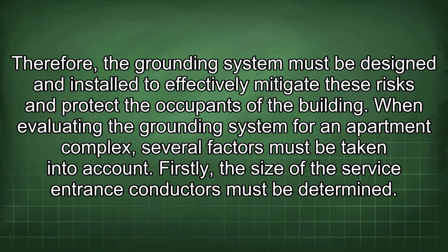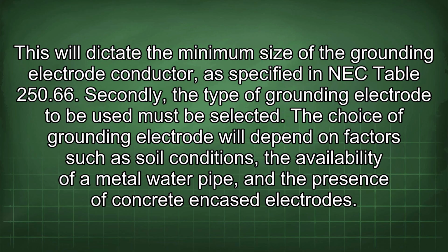When evaluating the grounding system for an apartment complex, several factors must be taken into account. Firstly, the size of the service entrance conductors must be determined. This will dictate the minimum size of the grounding electrode conductor, as specified in NEC Table 250.66. Secondly, the type of grounding electrode to be used must be selected. The choice of grounding electrode will depend on factors such as soil conditions, the availability of a metal water pipe, and the presence of concrete encased electrodes.